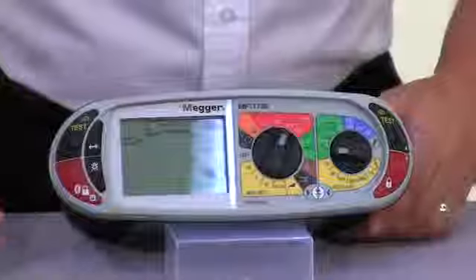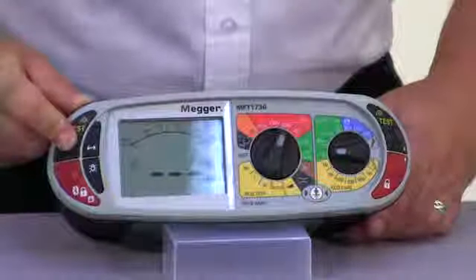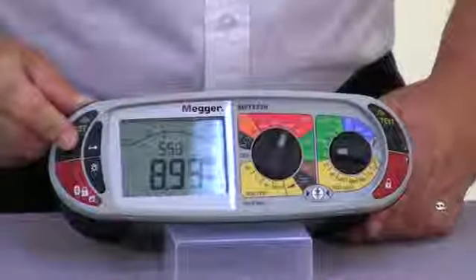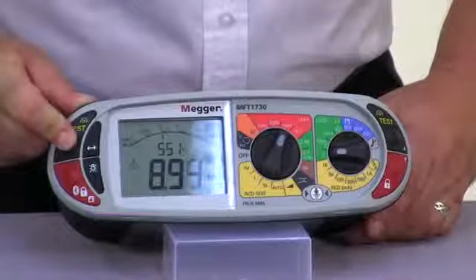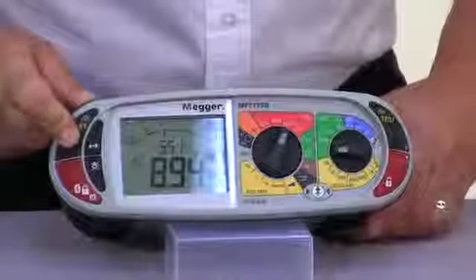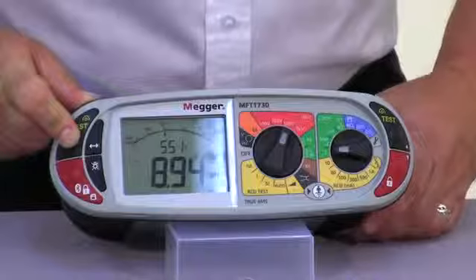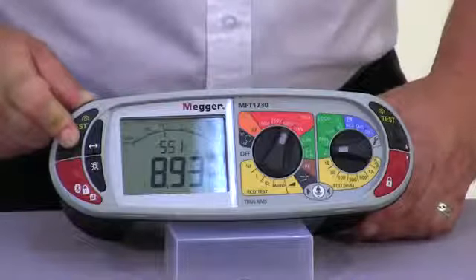So we have a known resistance, we've dialed 500 volt insulation, and we press the test button. Now the upper of the 2 parameters will now indicate to make sure that we're actually conforming with the 17th edition and maintaining our voltage output. And as you can see, we've got a reading here of 8.93, 8.94 megohm.